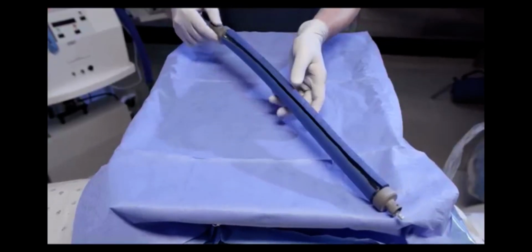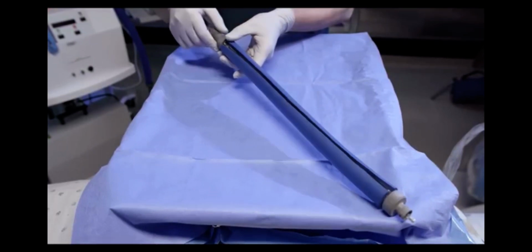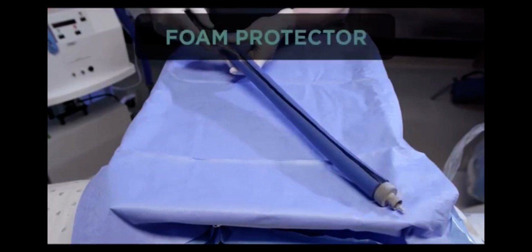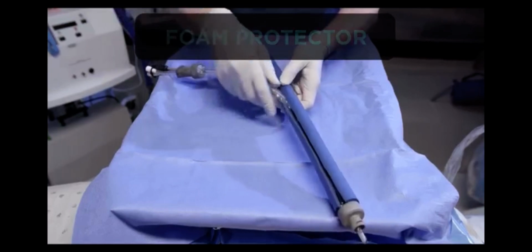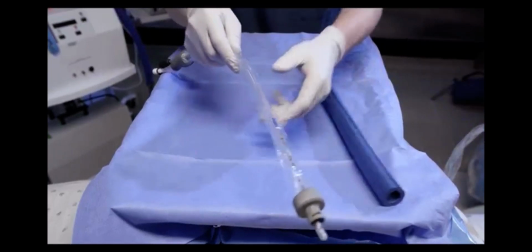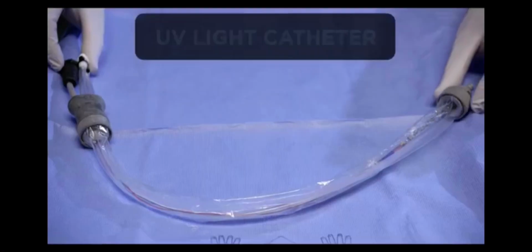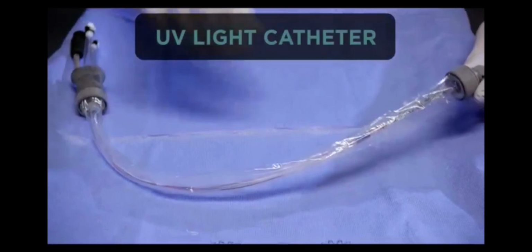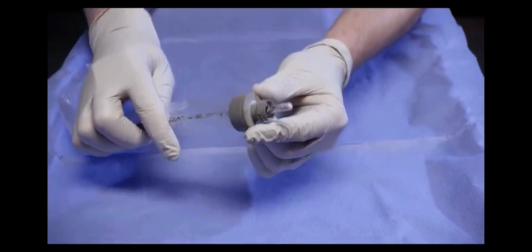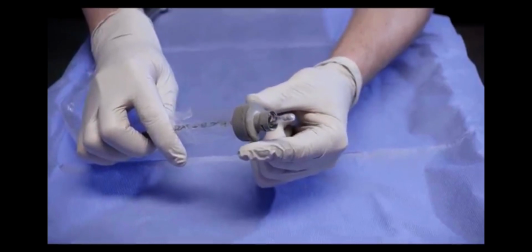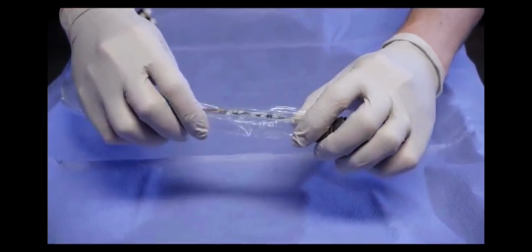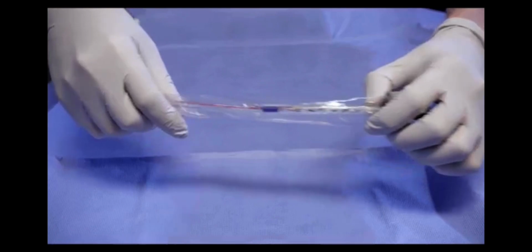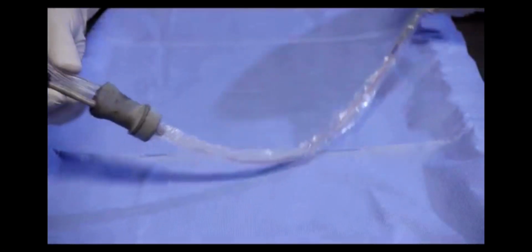The UV light catheter, when not in use, should be stored with a foam protector which is easily placed and removed for when the catheter needs to be in use. Here's the UV light catheter itself. Start at the distal end at the tip. We can see that that tip is sealed. Inside the most distal 10 centimeters of the UV light catheter are the lights themselves, as well as markings for how deep the catheter is inserted.